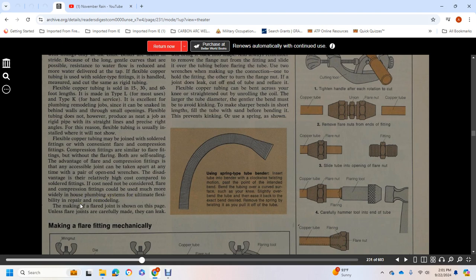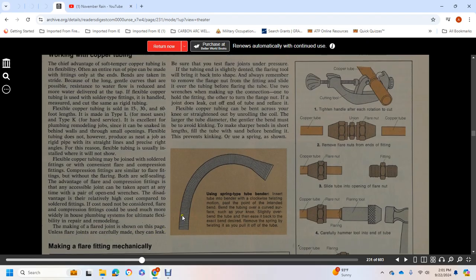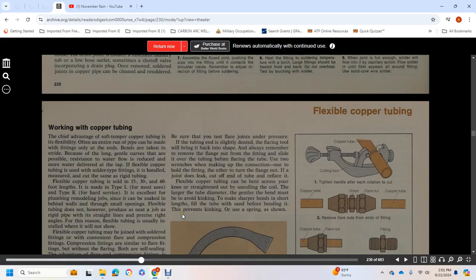Making a flare joint is shown on this page. The flare joints must be carefully made so you can be sure, so test flare joints under pressure. If the tubing is slightly dented, flaring the tubing will bring it back into shape. But always remember to remove the flare nut fitting and slide it over the tube before flaring the tube. Usually two wrenches make up the connection, one to hold the fitting, the other the flare nut. If the joint leaks, cut off the end of the tube and reflare it.